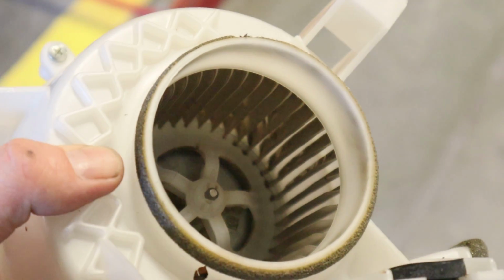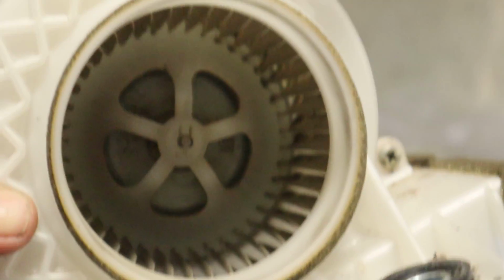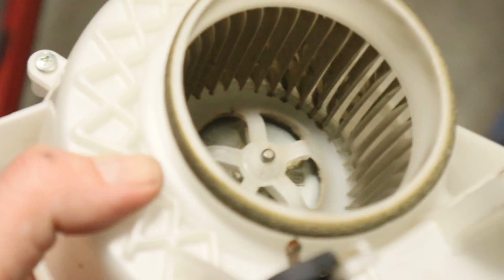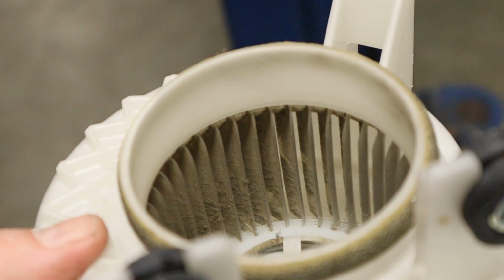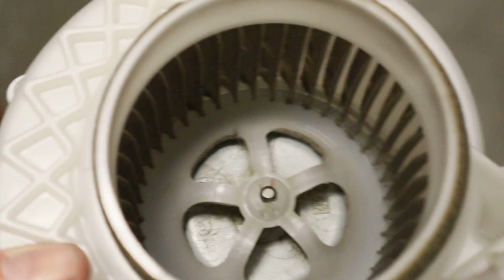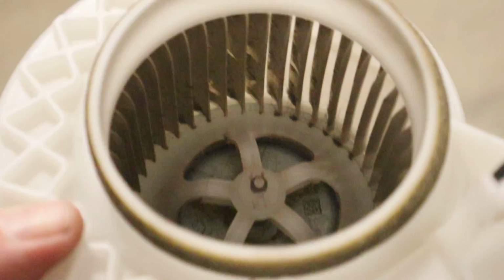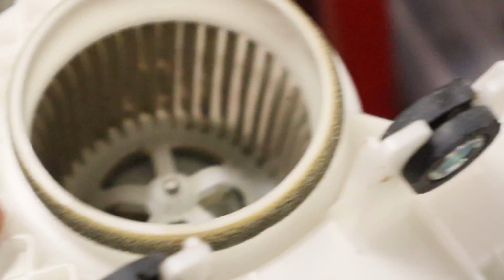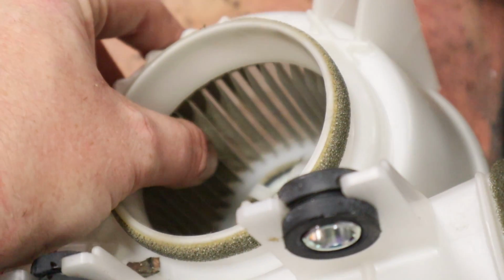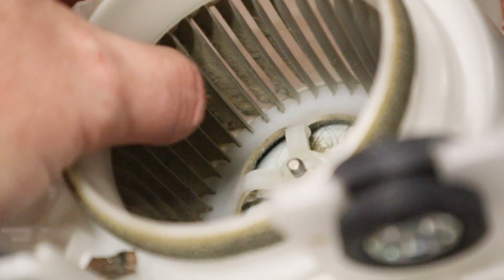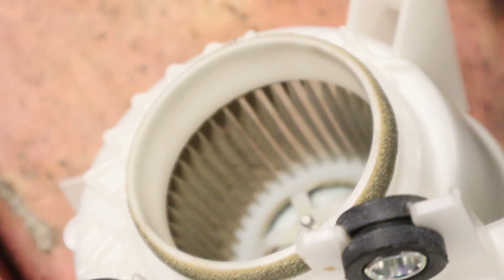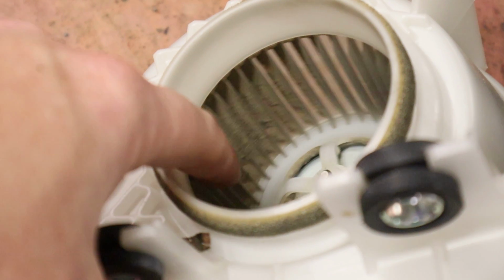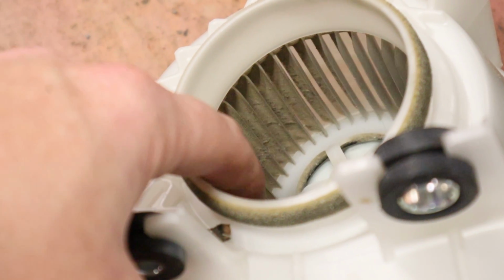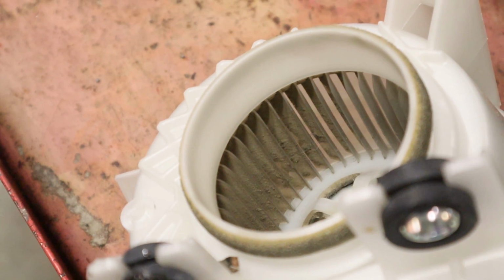What you don't want to do is spin this with air pressure, because it can overspin the fan and actually break the fan blades and shatter the fan on the inside. So if you're going to use air, hold the fan, then spray it with air, move it, hold it, spray it, and just move around to spray off each of these blades. After that, all you got to do is put it back together and we're good.